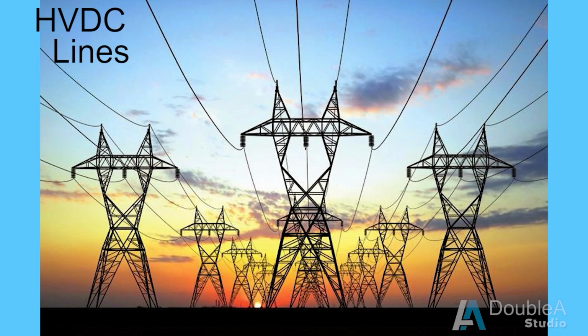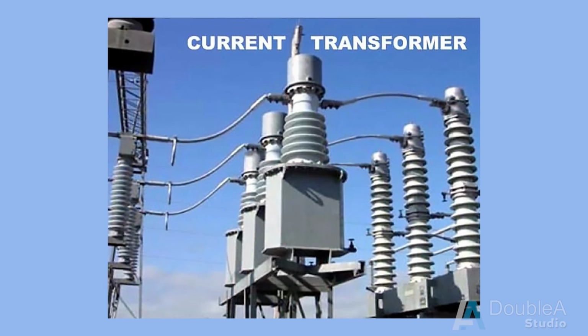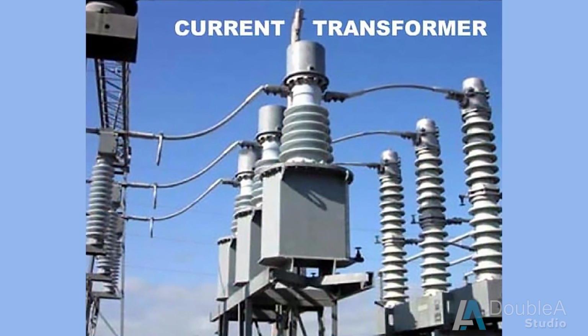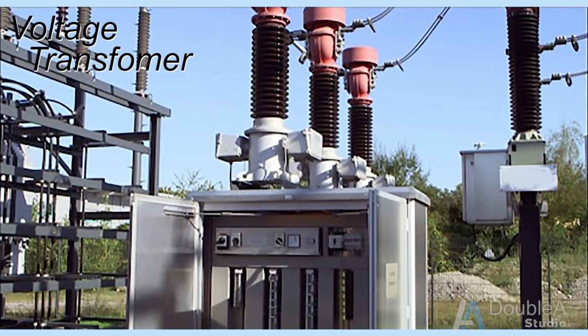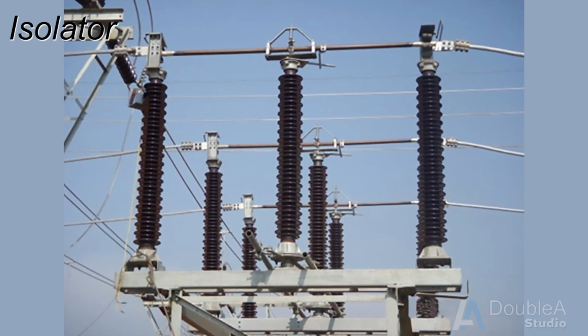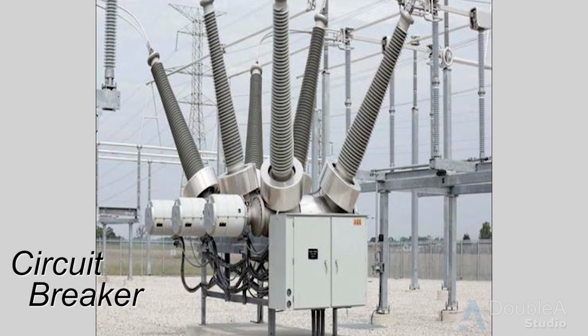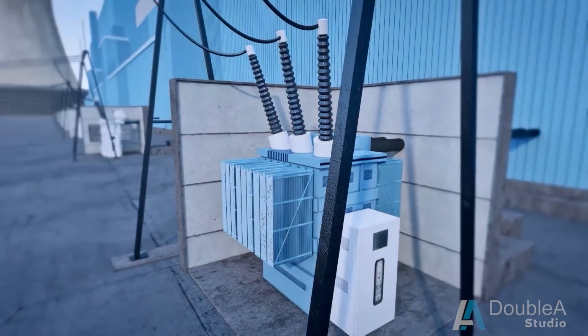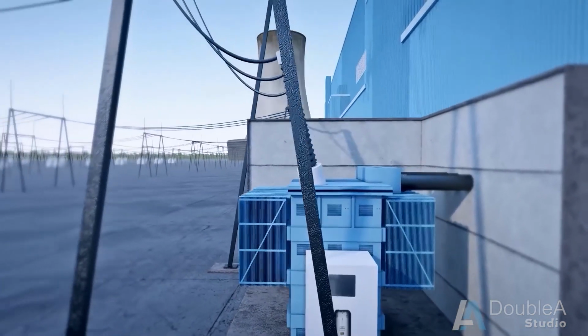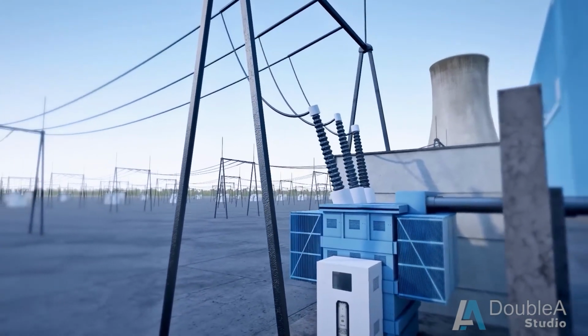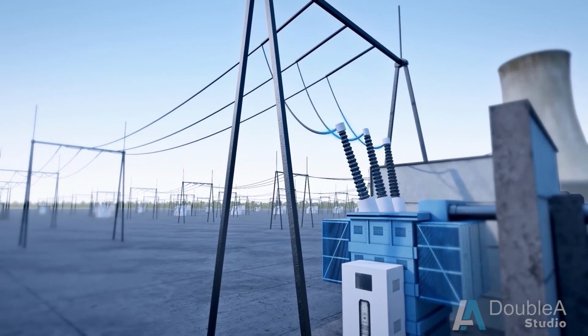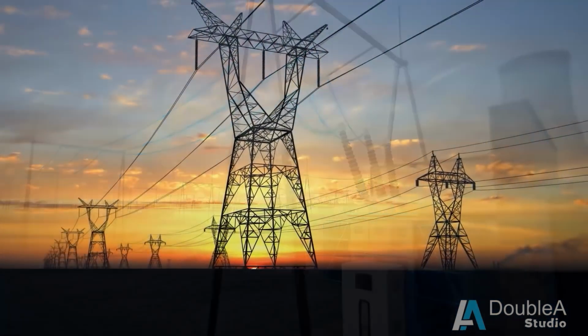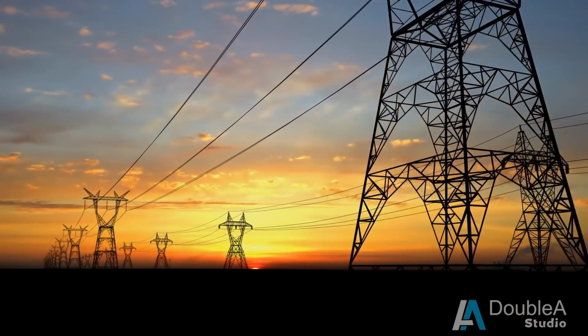From the generator transformer, stepped up power goes to the switchyard, which is equipped with current transformers, voltage transformers, isolators, circuit breakers, bus bars, and more. The main role of the switchyard is transmitting generated power to different load centers, connecting and disconnecting the transmission lines as per the requirement, protecting the transmission system by isolating faulty network, and maintaining system frequency within limits.